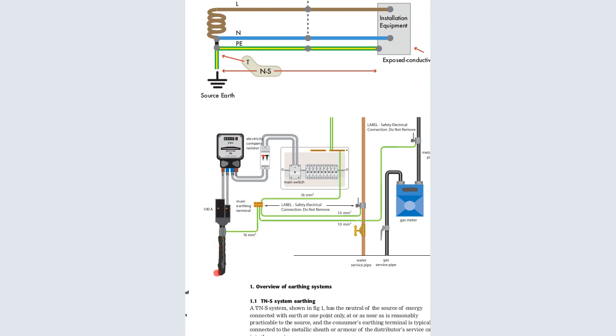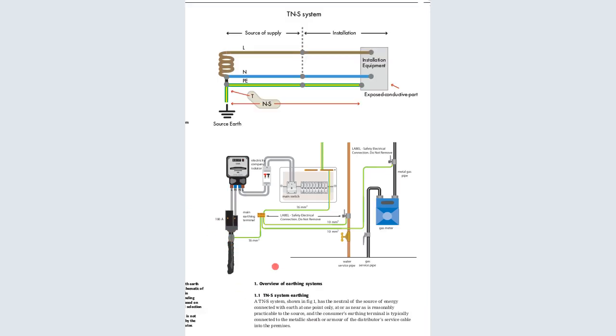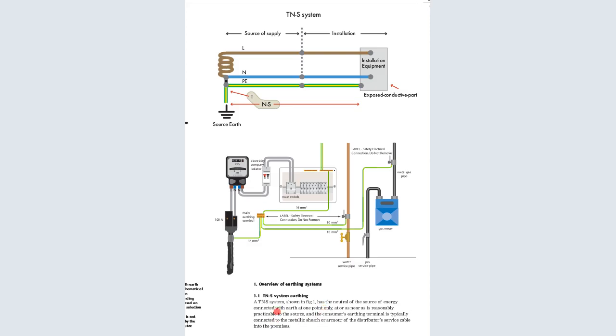So let us assume this is the electrode. So this is at 100 ampere live. So this is the live and this is the neutral. So they are all grounded at this point, and it goes to the earth.